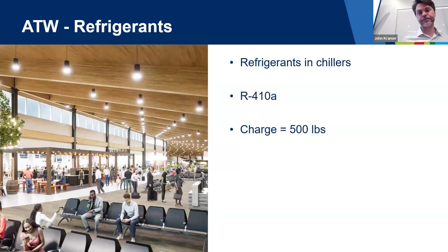And heat recovery chillers use a ton of refrigerant. So 500 pounds is a lot. A typical home air conditioner is probably under 3 pounds, unless you have a giant house. For a 2,000 or 3,000 square foot house that you're air conditioning, it's maybe 3 to 5 pounds of refrigerant. That is a lot of refrigerant. Here's kind of a graphic of what the heat recovery chiller might look like.